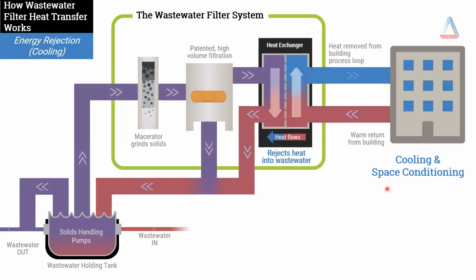Now, the next slide is where we're looking at energy rejection. So with this, it's very much the same process. All we're doing is moving energy in a different way. So in this case, again, using the color coding, the geofield or the building source is coming in at a much warmer temperature than the sanitary sewer source. So with this, we do the exact same process, move wastewater up through the system, filter the solids and get rid of them, using that filtered wastewater now as the heat sink. So moving energy across the wall of the heat exchanger from your geofield or your building system into the wastewater and sending it back to the sewer at a warmer temperature.